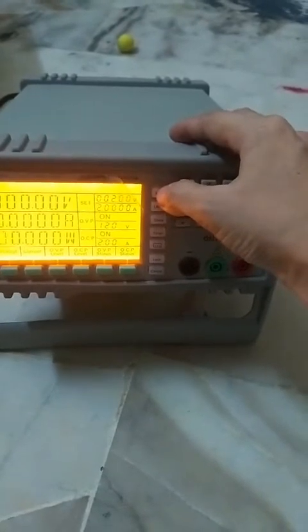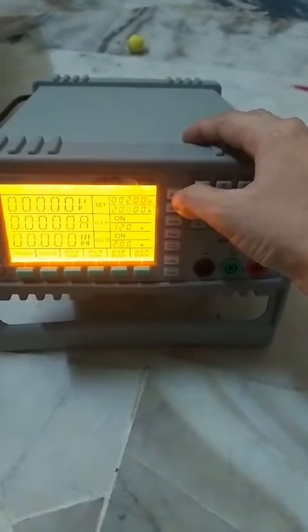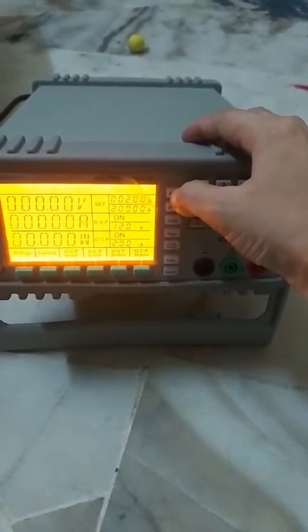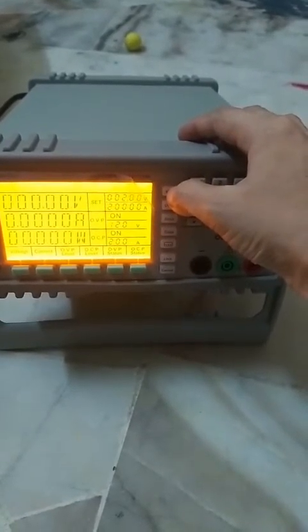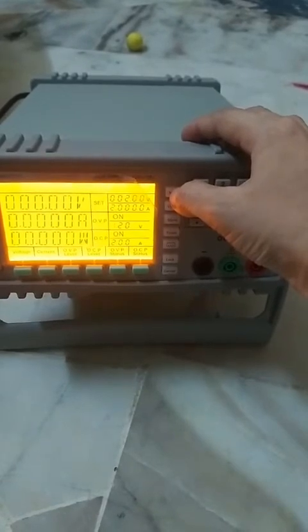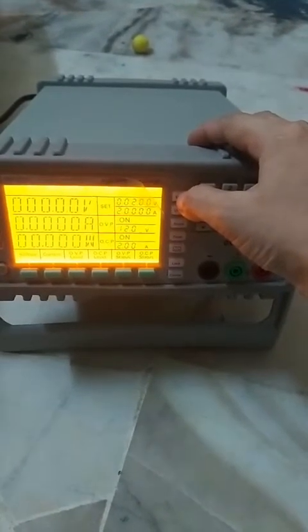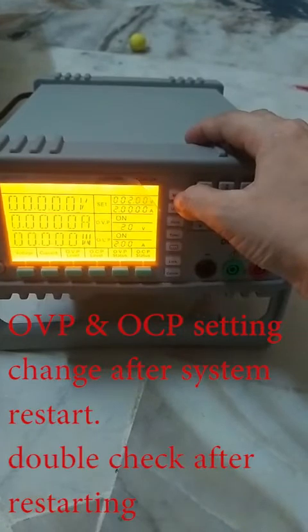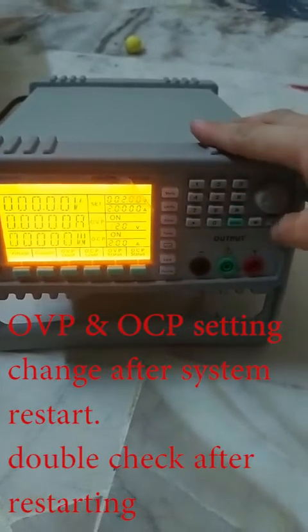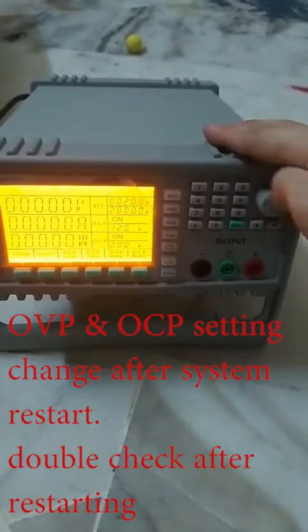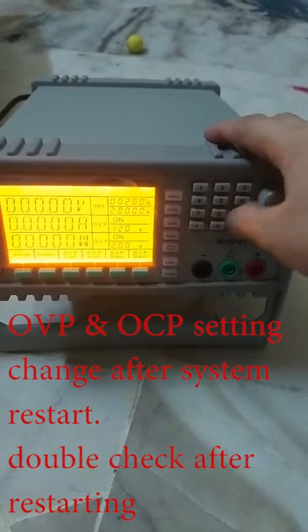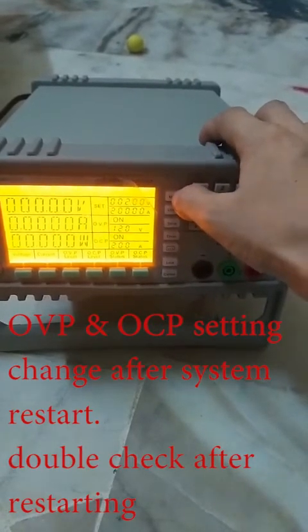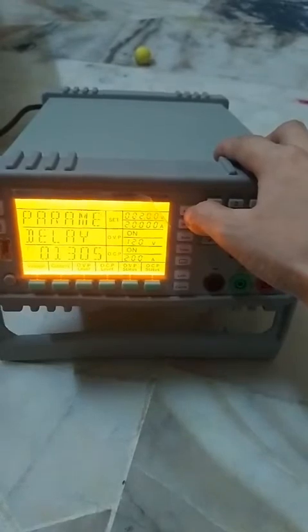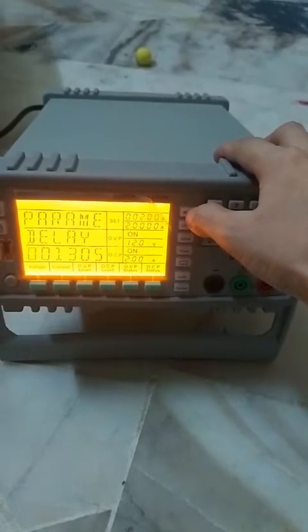Then click again to go into the current. In our constant voltage power supply mode, the current can be set to a maximum of 2. Then OVP we can make the same as the previous setting when we were using constant voltage. If you need to set it, you can choose the left and right keys and use the rotator, or you use the numbers to set the value. Then comes the most important parameter, the delay time.